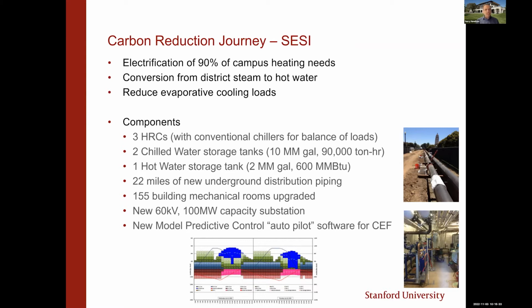I mentioned we had 3 heat recovery chillers. Of course, we have a large conventional chiller plant with evaporative cooling towers. We get probably less than 45% of our annual chilled water load from the heat recovery chillers. We're a cooling dominated campus, and our cooling load is only growing, which is a topic for another seminar, but we are seeing that.